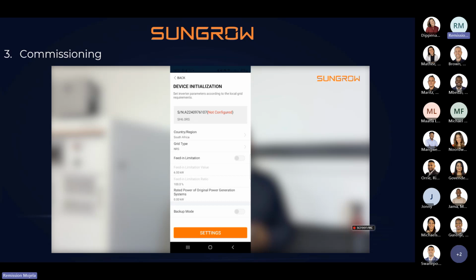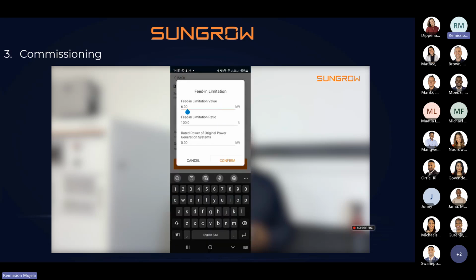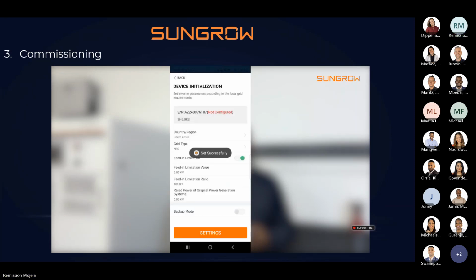One important thing is the feed-in limitation. If you want to feed back into the grid or limit it, you have to enable it. But if you're not allowed to feed back into the grid, you can change the feed-in limitation value to 0 and the feed-in limitation ratio to 0 as well. The last thing is to enable the backup mode. That needs to be enabled, or else the inverter will just shut down when the grid falls off. Then you enable the backup mode and press settings.